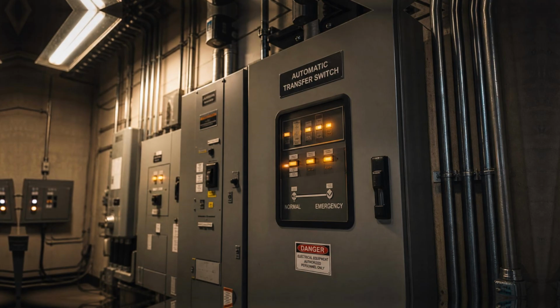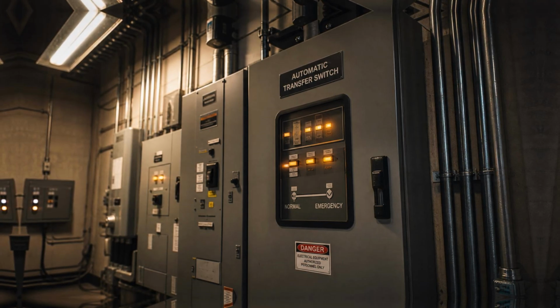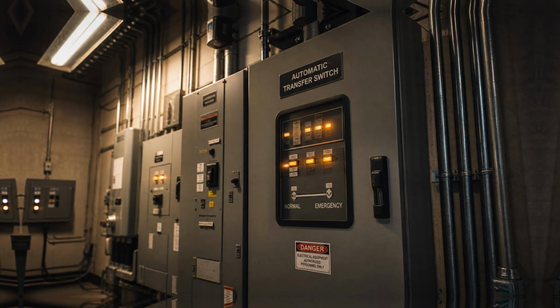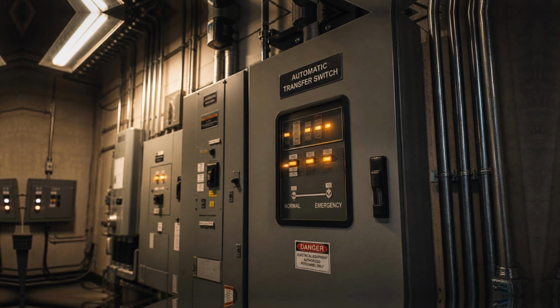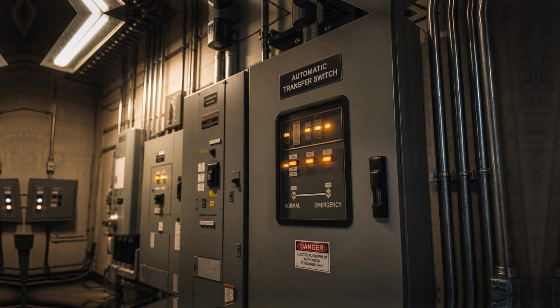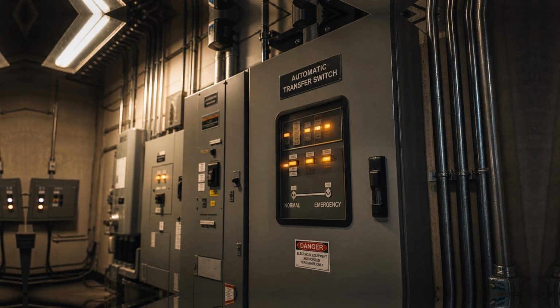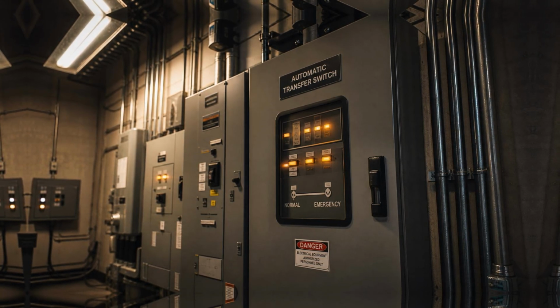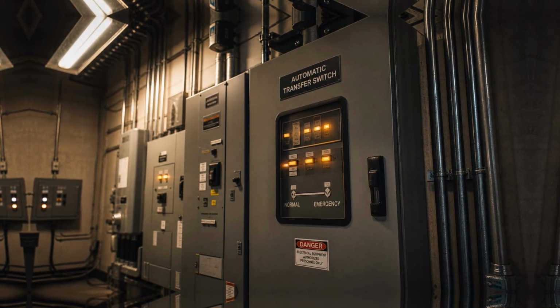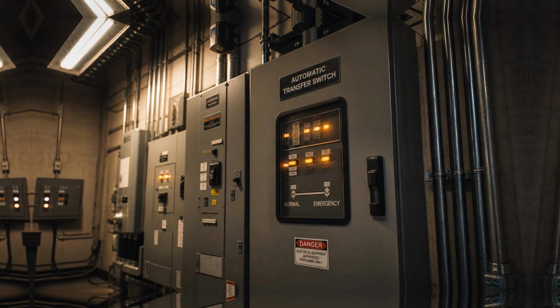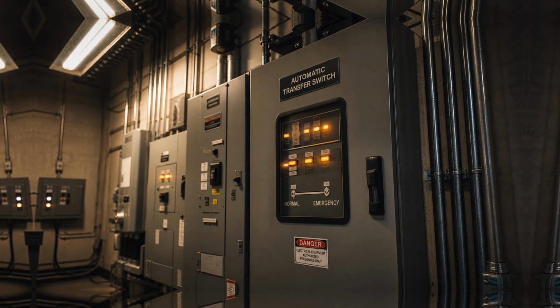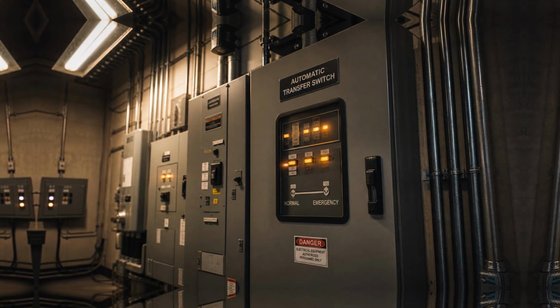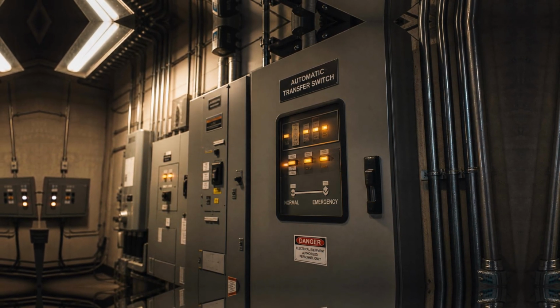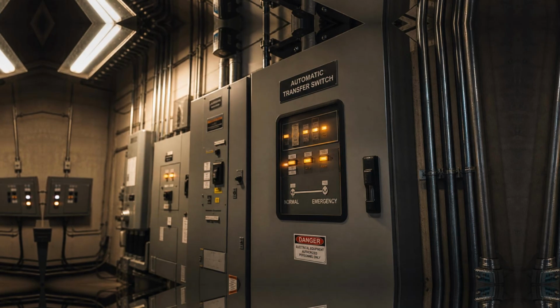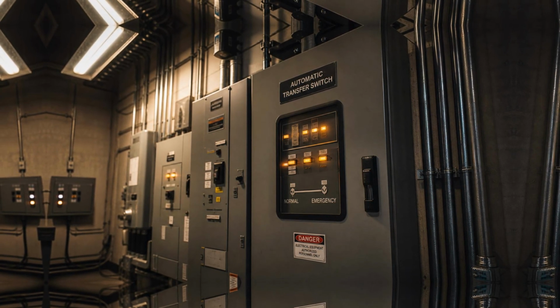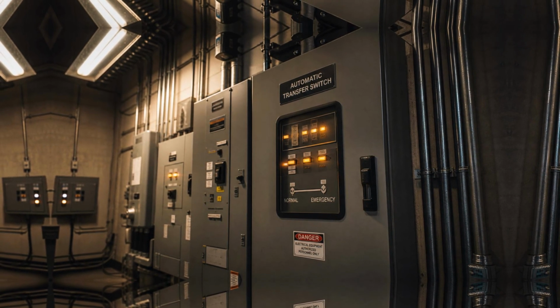Some buildings have one transfer switch. Some have many, a separate switch for each category of emergency load, arranged so that life safety circuits, critical care circuits, and equipment circuits can each be managed independently. In larger facilities, a room may be devoted to transfer switches entirely. A quiet space filled with gray cabinets, each one watching its portion of the building, each one ready to make its selection when called upon.